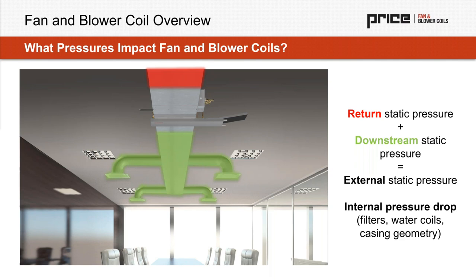Those two things together are really the engineer's responsibility to evaluate, because as we see external static pressure increase, we're going to see more power consumption and more sound generated. At Price, we're doing everything we can to reduce internal pressure drop as much as possible. So looking at low pressure filters, low pressure water coils, and lower pressure casing geometry. If we can reduce internal pressure, that allows for more available external static pressure for you guys to work with as design engineers.